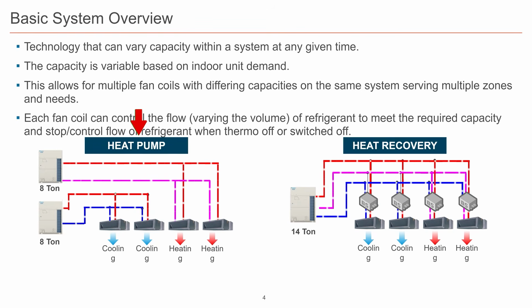So, all right, as you can see on the screen here, heat pump, very basic. It's either 100% in heating, or it's in 100% cooling, or it's right in the middle of off. There's nothing else fancy about that. There's two refrigerant pipes, like we're all accustomed to. Standard heat pump. Heat pump is a heat pump. We're not inventing something new. Heat recovery, on the other hand, is a different animal.